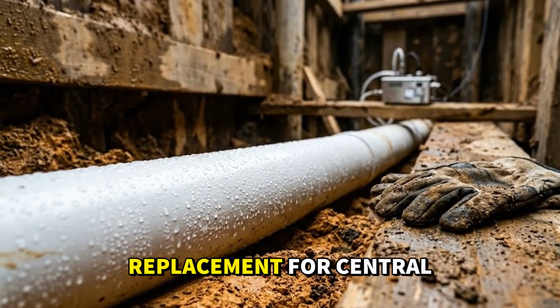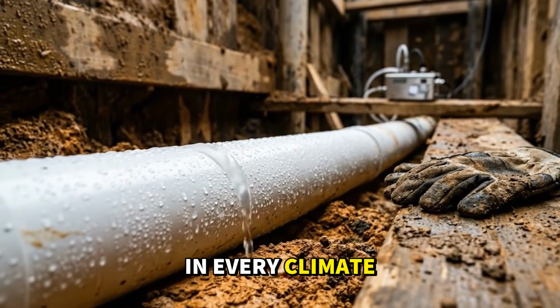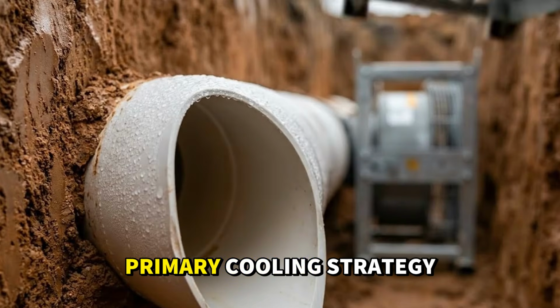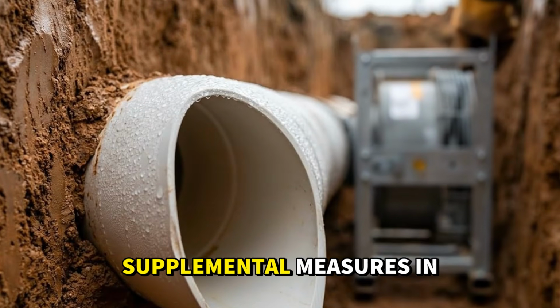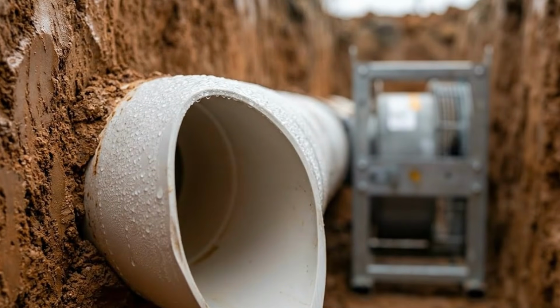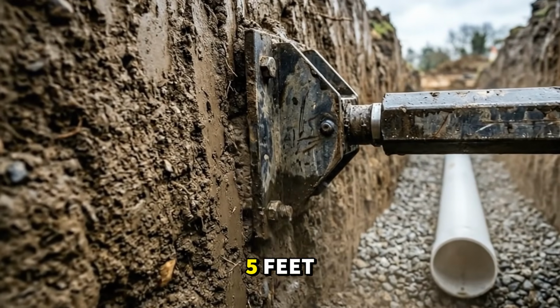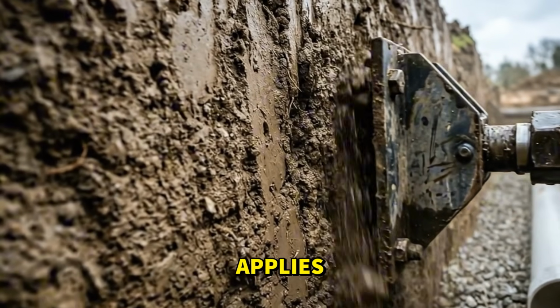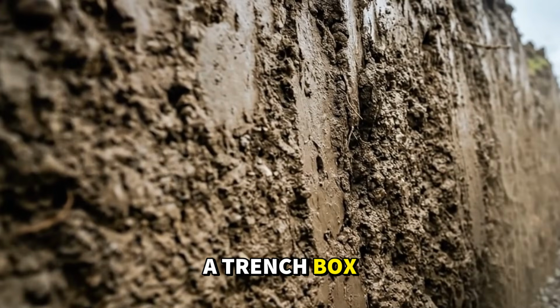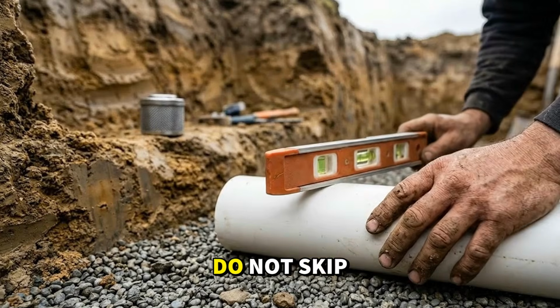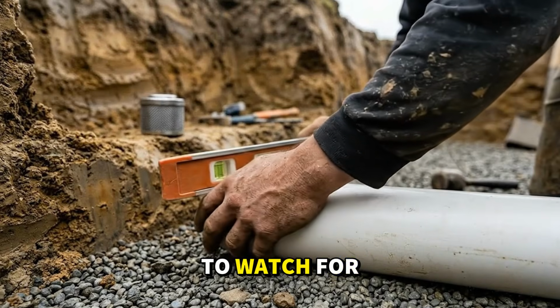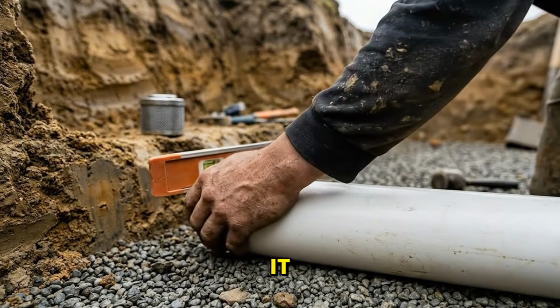This is not a drop-in replacement for central air conditioning in every climate and every situation. It is a primary cooling strategy that may need supplemental measures in extreme conditions. And if you are digging a trench deeper than 5 feet, OSHA trench safety applies. Sloping, shoring, or a trench box. A collapsed trench can kill you. Do not skip this. Now that you know what to watch for, here is exactly how to build it.